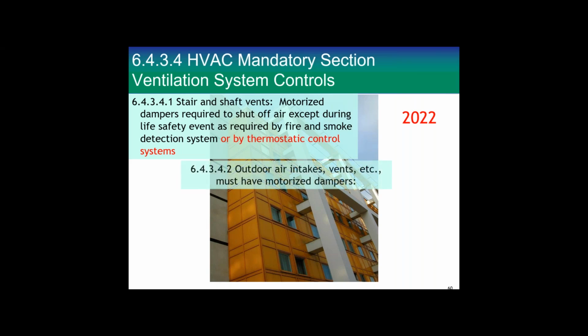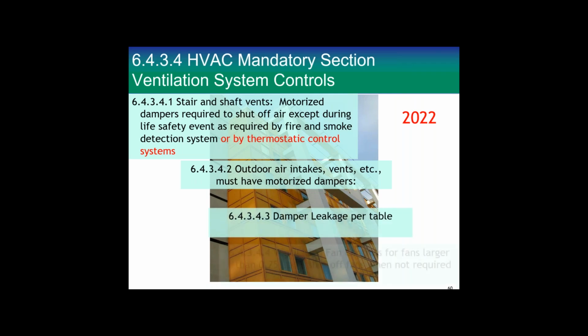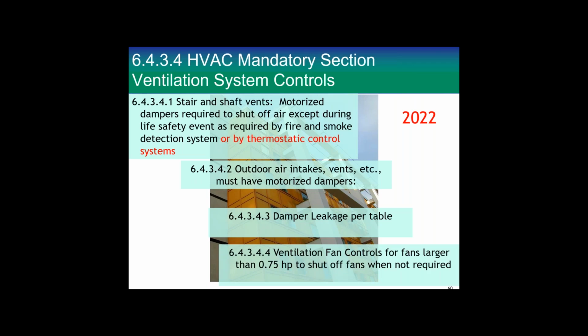We want to close the building up as tight as we can close it. So we want to close every damper we can close, as much as we can close it. Outdoor air intakes, vents, etc., must have motorized dampers. Damper leakage per the table, you'll see in a minute. Ventilation fan controls for fans larger than 0.75 horsepower shut off fans when not required.